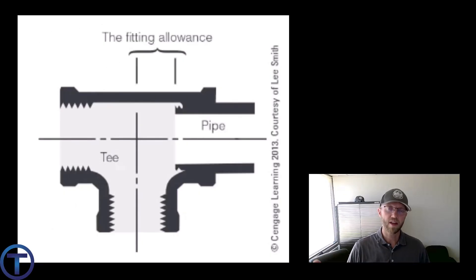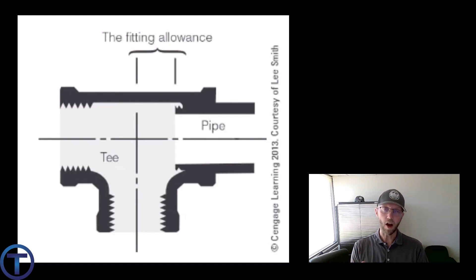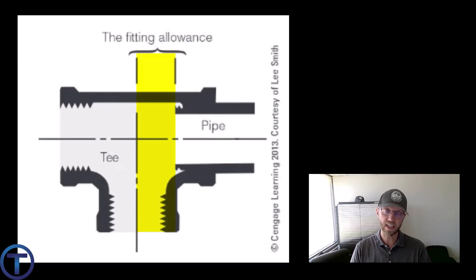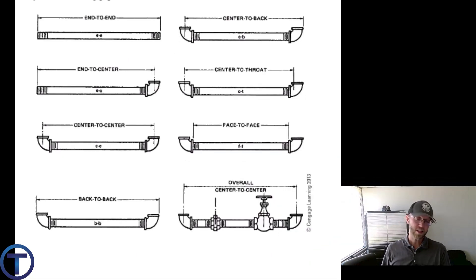Unit 8 gives us another illustration of a fitting allowance on a threaded T. You can see the T with the center line of pipes marked. On the right side, the pipe is coming into that T. You can see where that pipe stops, and the space between the end of that pipe and the center line of the fitting — that's the fitting allowance. That's what we subtract from our center-to-center to get our cut.